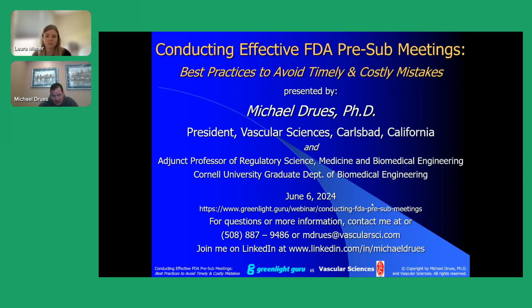But I have a situation right now where the company wants to go back to the FDA with pre-sub supplements on 2 or 3 different topics, because certain divisions within CDRH will allow overlapping pre-subs and others will not. Find out from that division if you can have overlapping pre-subs or overlapping pre-sub supplements. If you can, then great. If you cannot, then in my particular customer's case, what we've done is, even though the 3 topics that we want to talk further about were in the original pre-sub, we're not submitting them as pre-sub supplements because they would have to be submitted sequentially in series rather than parallel.